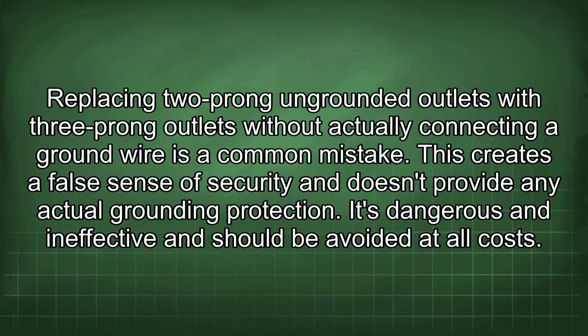Replacing 2-prong ungrounded outlets with 3-prong outlets without actually connecting a ground wire is a common mistake. This creates a false sense of security and doesn't provide any actual grounding protection. It's dangerous and ineffective and should be avoided at all costs.